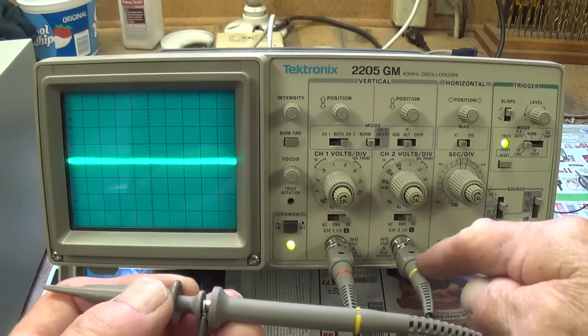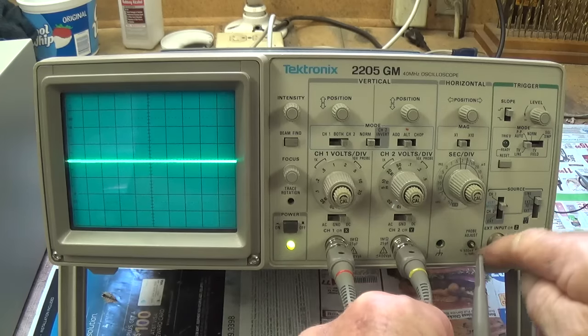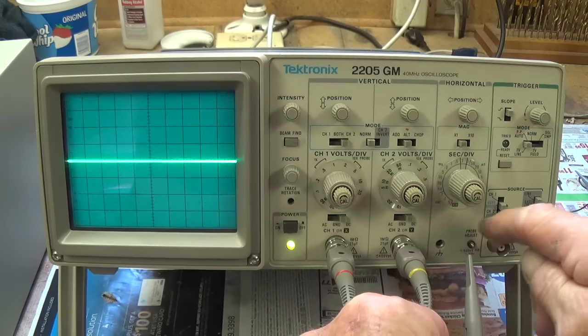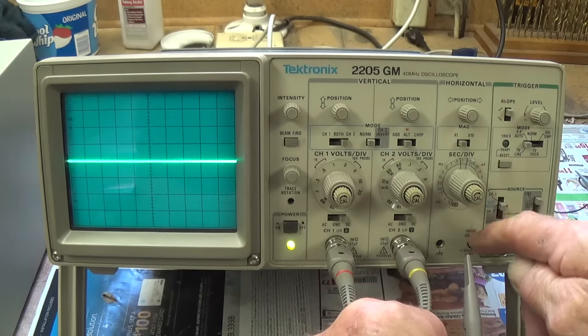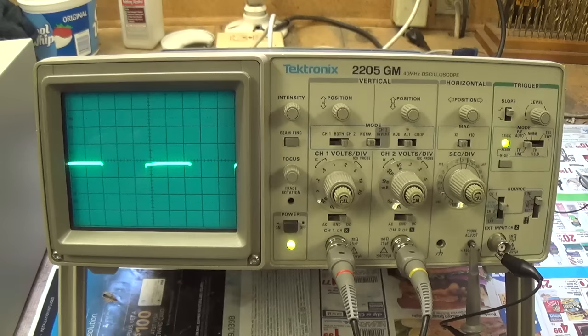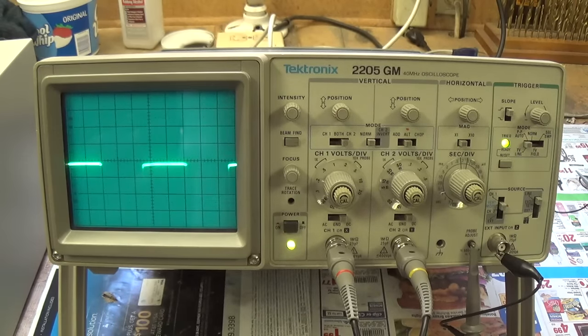Now, I'm going to take my yellow, yellow test probe and hook it up down there to the probe adjust lug to receive a 0.5 volt square wave. Okay, I'm all hooked up. This doesn't look like the other one did. So what do you think?